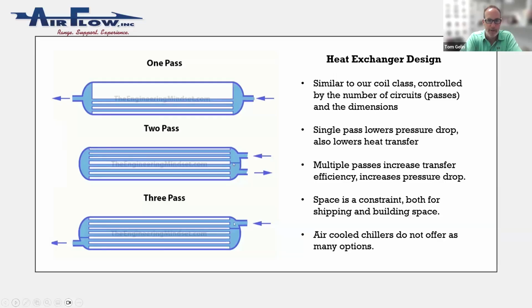Like we talked about, generally 2 pass for air-cooled chillers. And then when you get into the multiple passes, that's more for water-cooled systems where you're trying to fit more dimensionally. So you can shrink the footprint of a chiller by going to more passes, change the efficiency by going to fewer passes. Anything you want to add there, Ahmad?